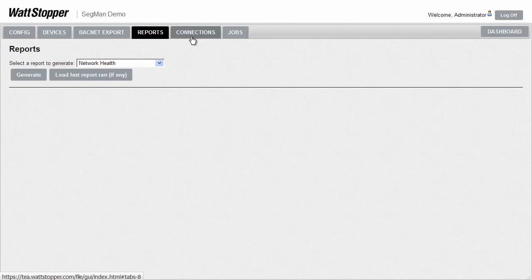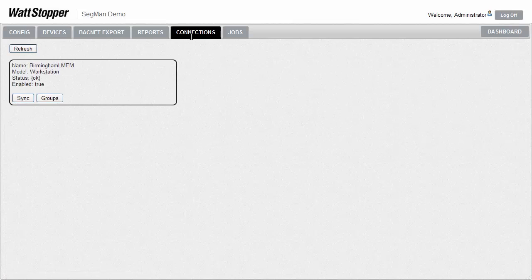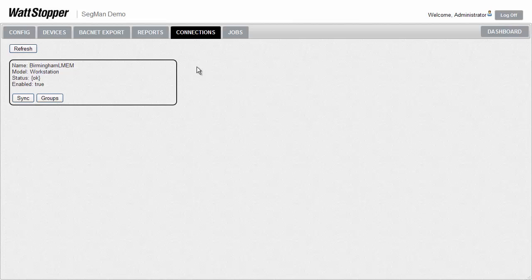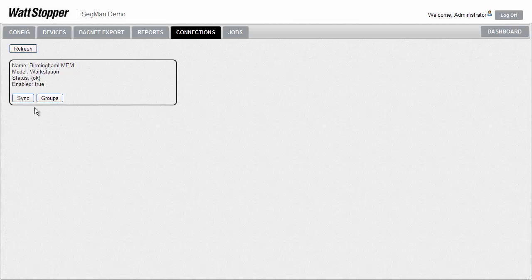There are two more tabs. Segment managers don't usually have a lot of memory to store much history information. If this segment manager is part of a larger installation with other segment managers, it might be communicating up to a supervisor. A supervisor is basically the segment manager software, but running on a full server with tons of hard drive space. The supervisor can pull and store the history of every room and other parameters for long periods of time from multiple segment managers, possibly from one or more buildings or sites. The connection tab gives us an easy way to see which supervisor, if any, is communicating with. The sync and group buttons make it easy to update the info in the supervisor if anything has changed here in this segment manager.